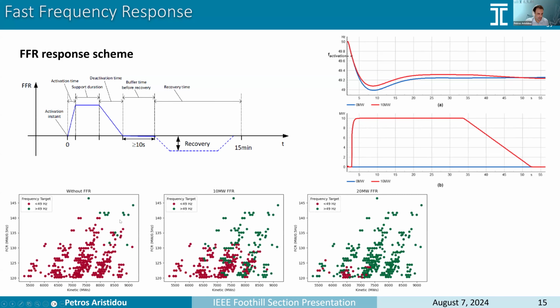If we see again different scenarios from the Cyprus system, we can see the first schematic on the left without fast frequency response. We can see here that most of these scenarios are not secure. So the nadir goes below 49 hertz. And if we add 10 megawatt of fast frequency response, the same exact scenarios with the same FCR and the same kinetic energy, half of them become secure. And if we add 20 megawatt of fast frequency response, we see that the majority of them become secure.